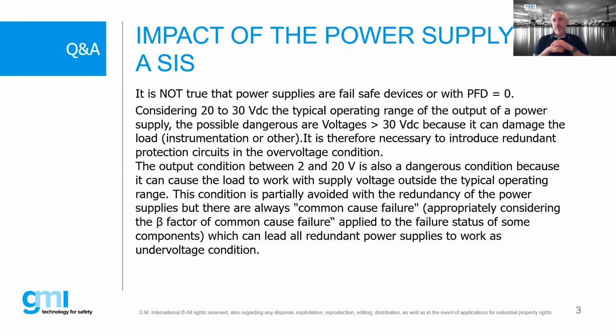We already saw, and Massimo explained very well, that 20 to 30 volts is the typical operating range for a power supply, and dangerous failures occur when the voltage is higher than 30, because this situation can cause real problems on your instrumentation. So it is very important to have redundant protections that block and stop an overvoltage situation above 30 volts. An output condition between 2 and 20 volts is also critical, because the loads are working out of specification. You can have malfunctions, and the instrumentation may not work properly.